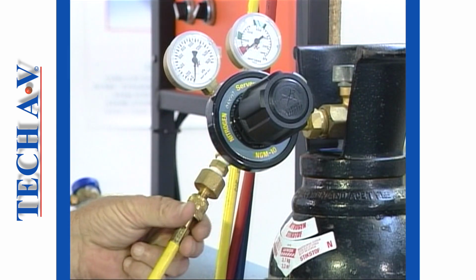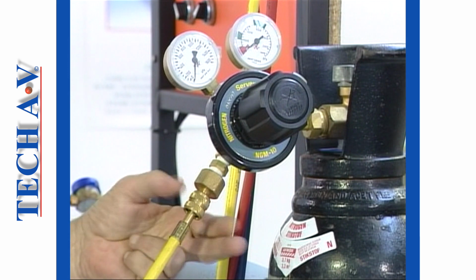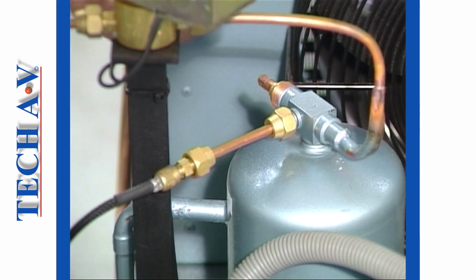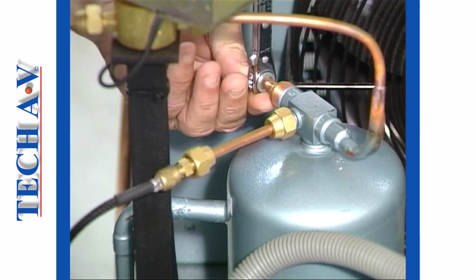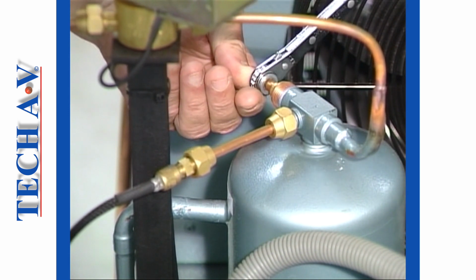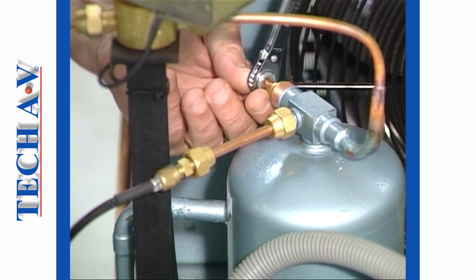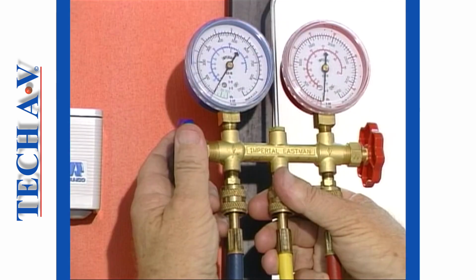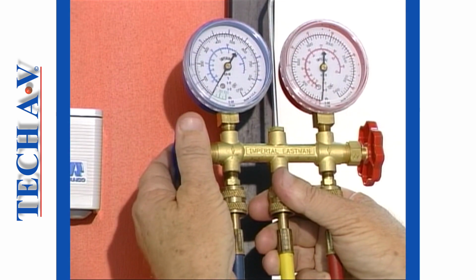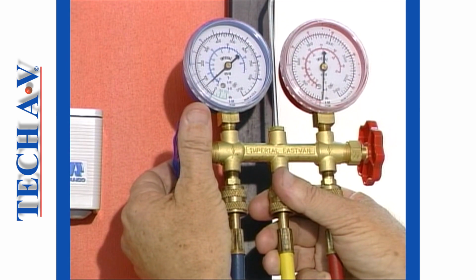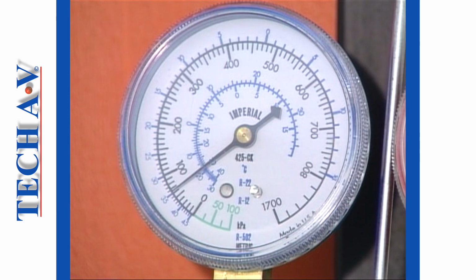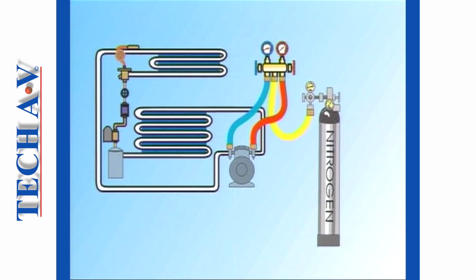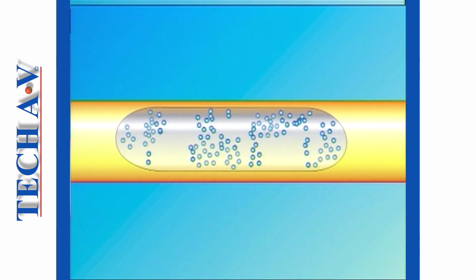The yellow connection is then swapped over to the nitrogen cylinder. To avoid damaging the analyzer, we must backseat the service valve as we're going to introduce pressure. Via the gauge manifold, we next allow a nitrogen charge of around 60 kPa to enter the system. The system is left to stand for about an hour. During this time, moisture will be absorbed into the dry gas.